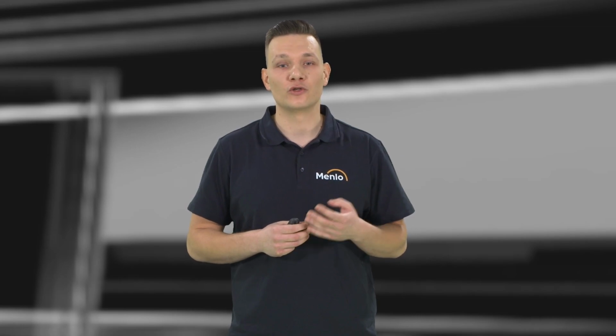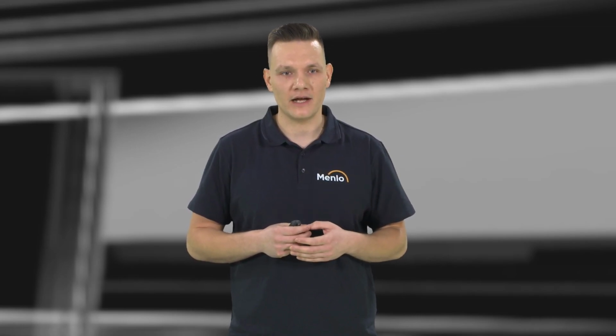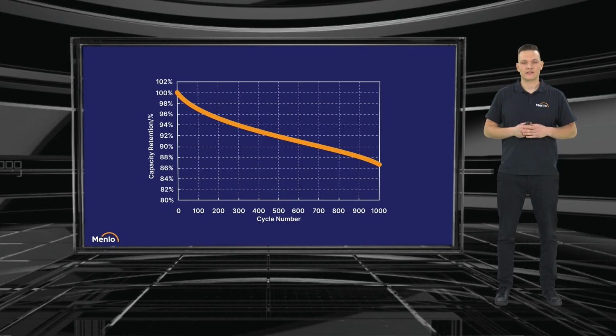So it is important to pay attention if the producer is referring to usable energy or to the capacity of the battery. This graph represents capacity retention as a function of cycle number. A cycle is charging and discharging the battery to the fullest, but usable energy, of course. So you always need to check the warranty of a producer and see what capacity they guarantee after a specific number of cycles. For example, it can be 80% after 4,000 cycles or 70% after 6,000 cycles. These are things that you should look at in the warranty of the battery.